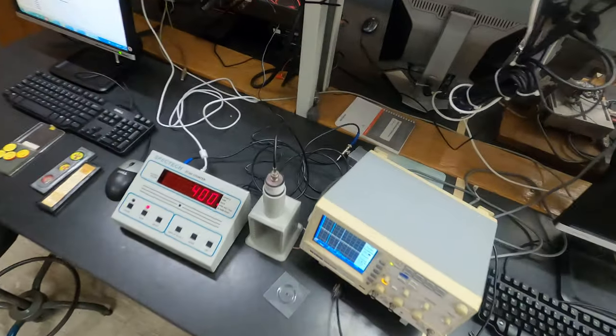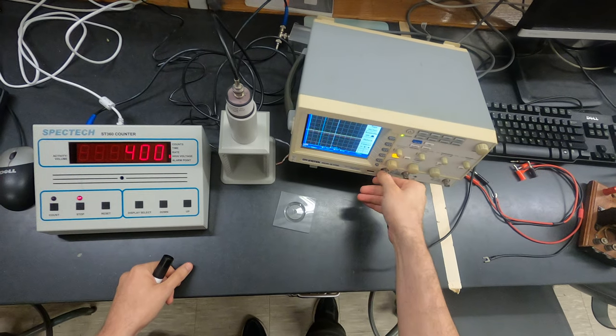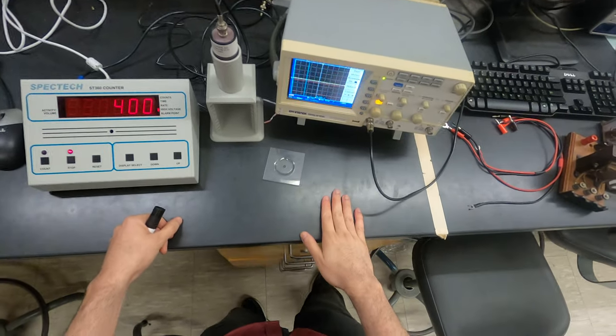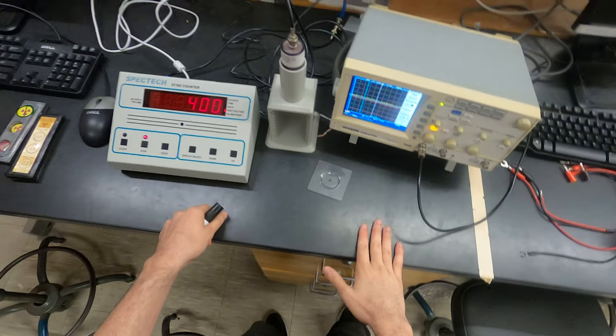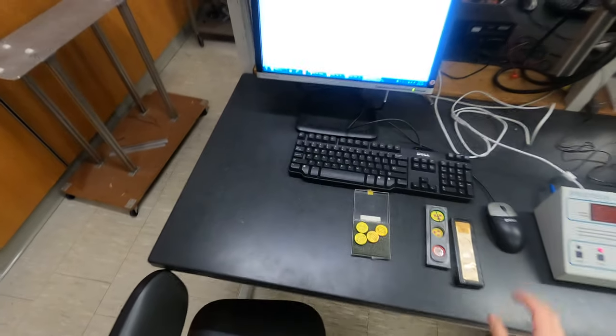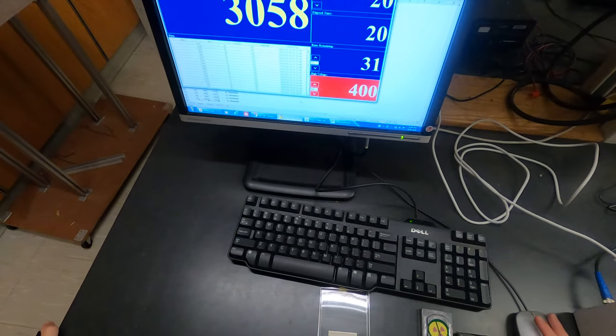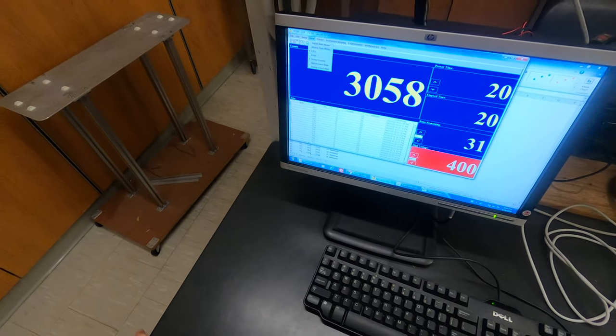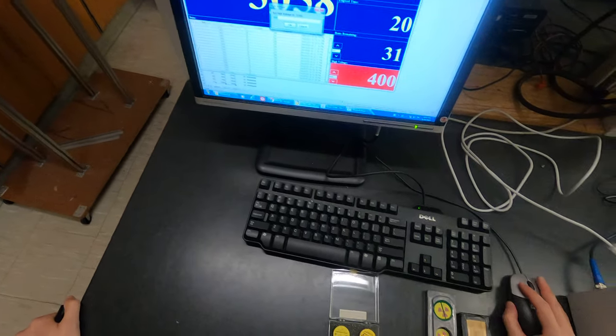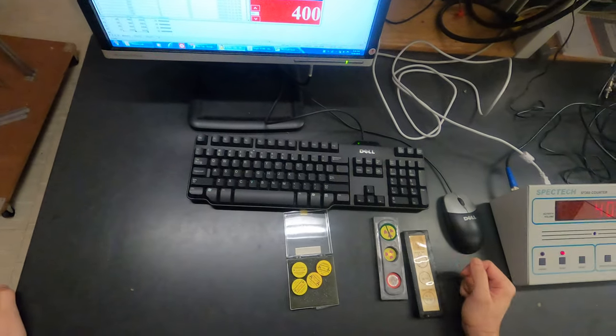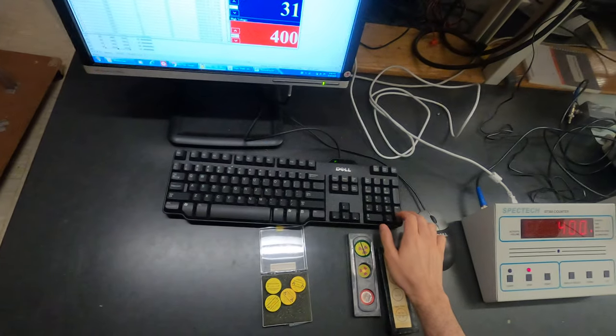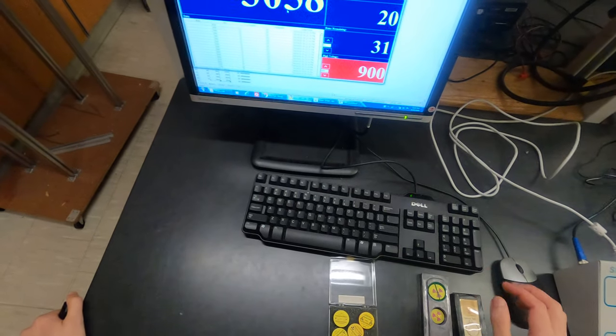We have a cable here, an output cable that you can connect to your oscilloscope. Right now I don't see any counts, so let me increase the voltage in the detector. You can come here, setup HV settings, and we have to work within the plateau region. So let's say 900 volts.